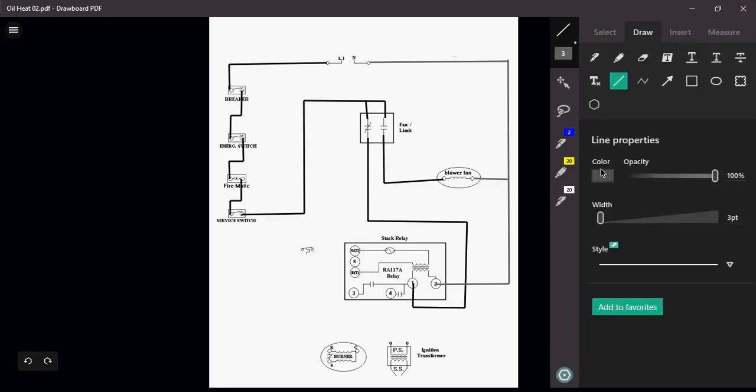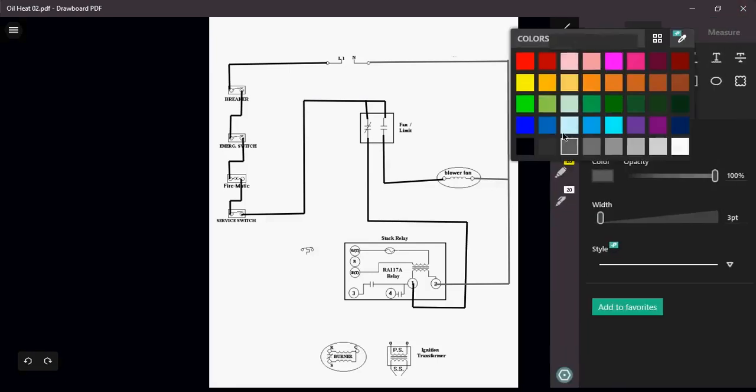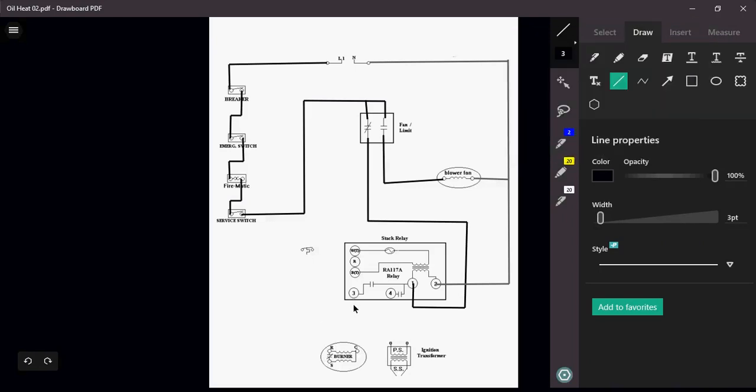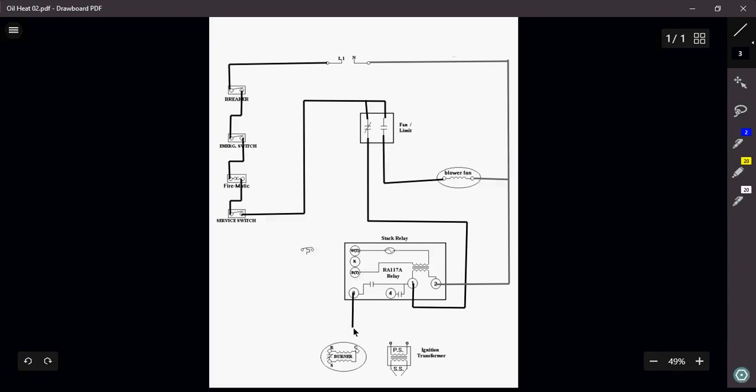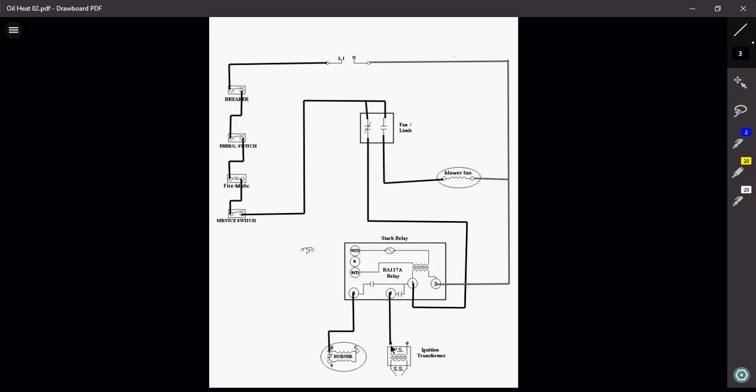So all I need to do with this type of diagram is just bring my power from my terminal 3, and I'm just going to bring that right in to my burner. I'm going to do the same thing with terminal 4. I'm just going to bring that straight down. I'm going to power up my ignition transformer.